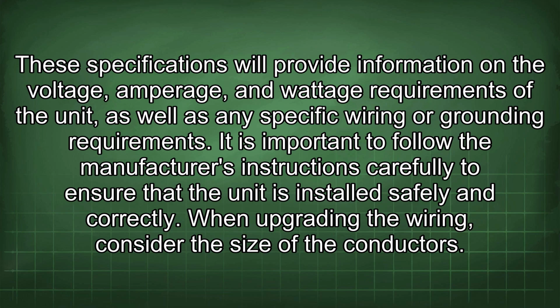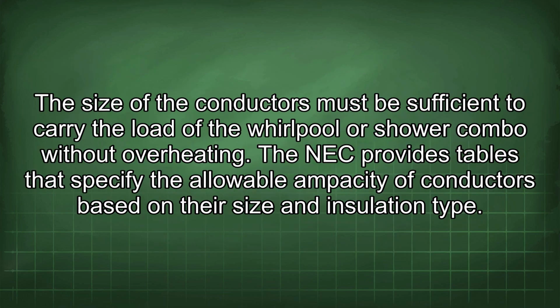When upgrading the wiring, consider the size of the conductors. The size of the conductors must be sufficient to carry the load of the whirlpool or shower combo without overheating. The NEC provides tables that specify the allowable ampacity of conductors based on their size and insulation type.